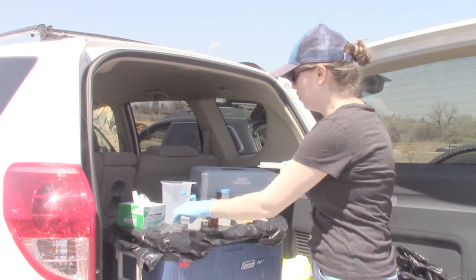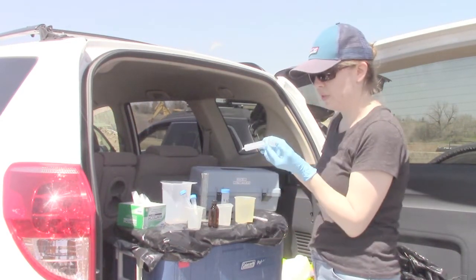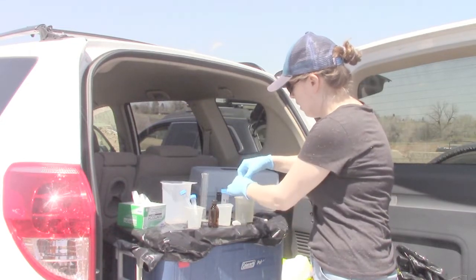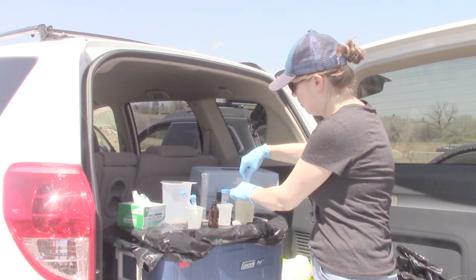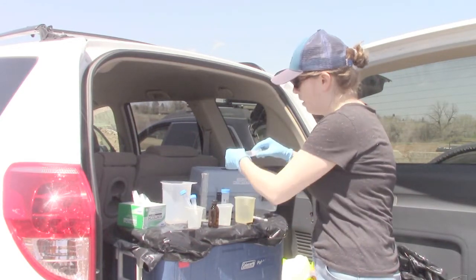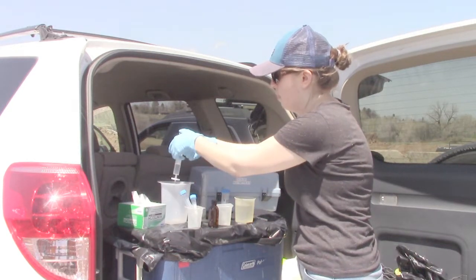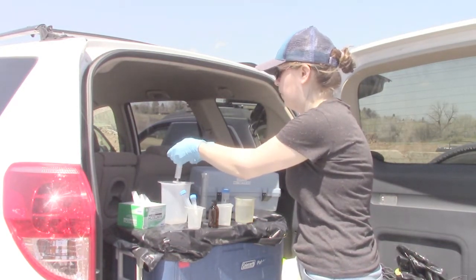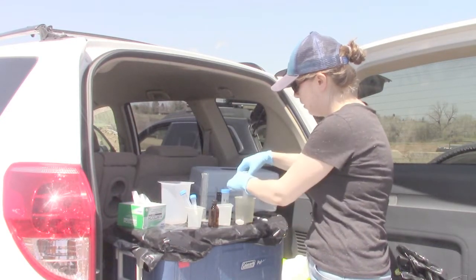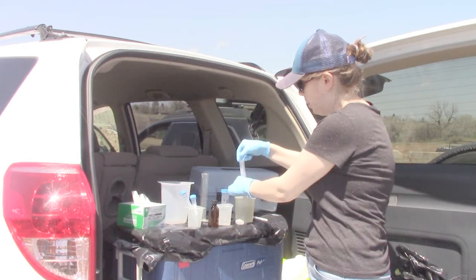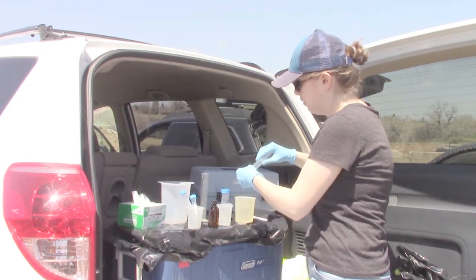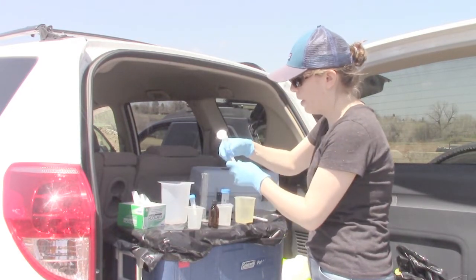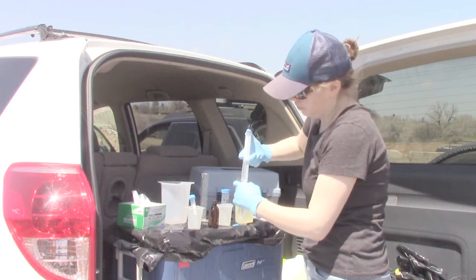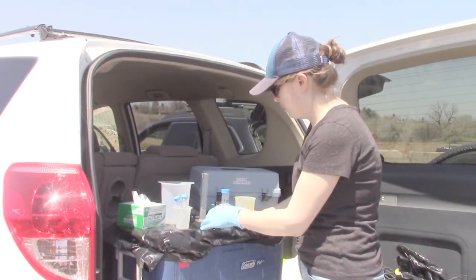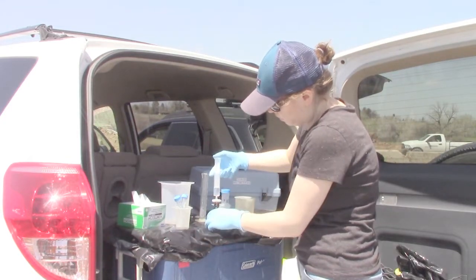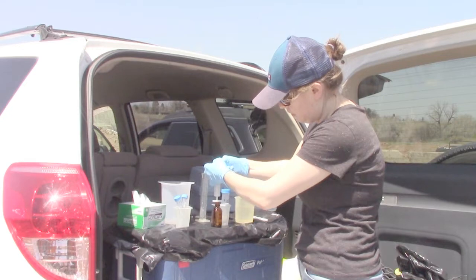So what I'm going to do is, first we need to rinse the syringe and the filter. It's a 0.45 micrometer filter. So I will fill the syringe up a little bit more than halfway, and then rinse the filter into my waste bin. Once I've done that, I'll take another sample. I can start filling the different vials. So I'm going to start with dissolved metals. And the next one is the 60 ml for the anions and dissolved organic carbon and chemical oxygen demand.